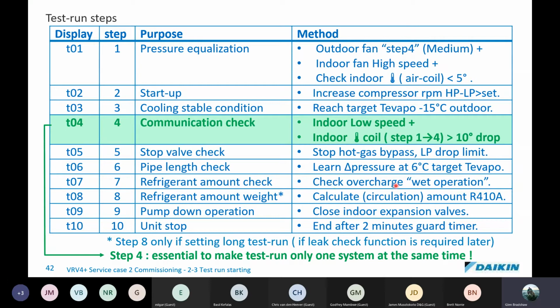How do you check the operation of the wet operation, or where it's slugging liquid? There's another term that you might hear. Basically, it looks at the discharge temperature, and if that discharge temperature falls below a certain value, it will indicate that there's liquid coming back onto the compressor. Okay, so just remember, high discharge temperatures normally indicate an undercharge. Low discharge temperatures or temperature differences would indicate that we have an overcharge condition, okay, or liquid floodback as well.